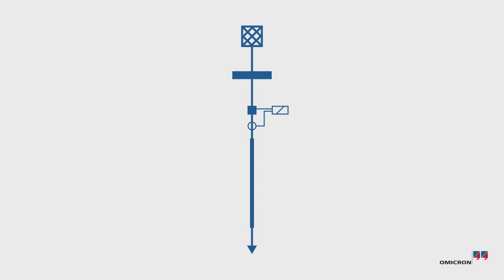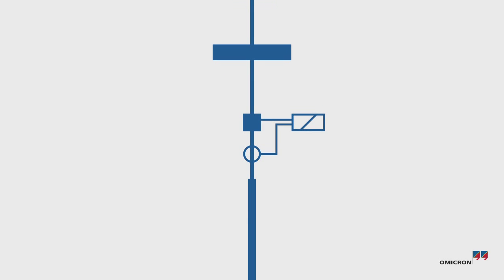We will test the auto reclosing function of a line protection relay as an example. We assume that there is a persistent fault. The relay under test will attempt to reclose twice, and we expect the relay to lock out after two reclosing attempts.